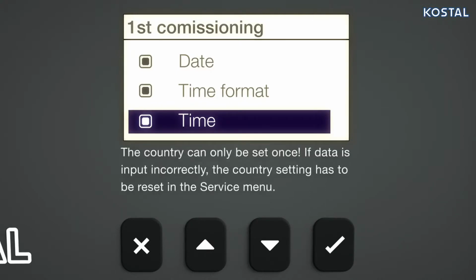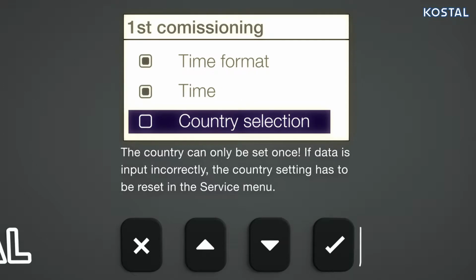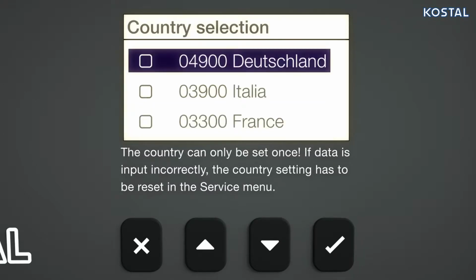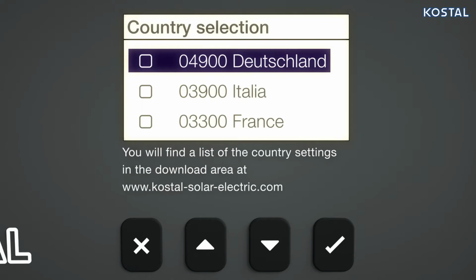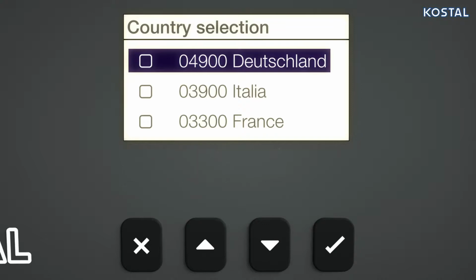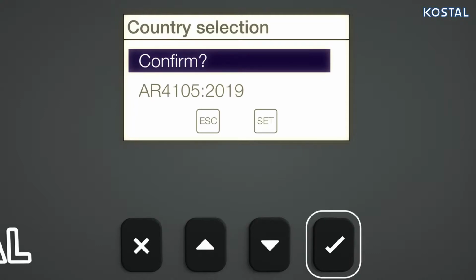Highlight Country Selection in the checklist. Set the country in which the inverter is installed and confirm the input. The inverter automatically loads the grid parameters stipulated for the country. Use the Set button to confirm the country selection, and keep this button pressed and held for approximately 3 seconds for your input to be adopted.